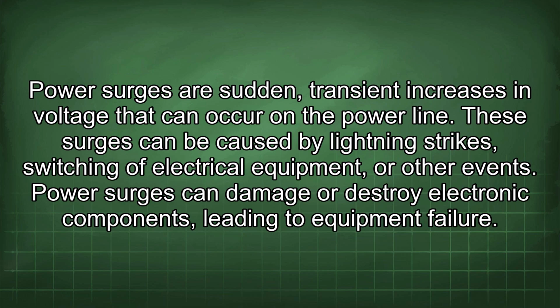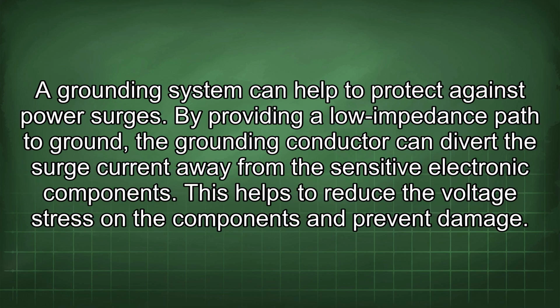Power surges are sudden, transient increases in voltage that can occur on the power line. These surges can be caused by lightning strikes, switching of electrical equipment, or other events. Power surges can damage or destroy electronic components, leading to equipment failure. A grounding system can help to protect against power surges. By providing a low impedance path to ground, the grounding conductor can divert the surge current away from the sensitive electronic components. This helps to reduce the voltage stress on the components and prevent damage.